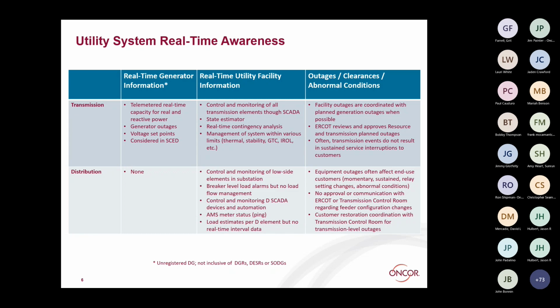It's mostly at the substation level, so if the feeder load and the back generation cancel out, then potentially there is no problem. It depends on the device at the individual levels, whether it's a device on the distribution system itself, such as the feeder breaker, or some device inside the substation, such as transformer protection or anything else. The capabilities and the settings of that device determine what actions occur upon different events on the grid. And will settings be changed to allow it? Sometimes it is a matter of changing settings. Sometimes it is replacement of a device with another device that has the capability that you need.